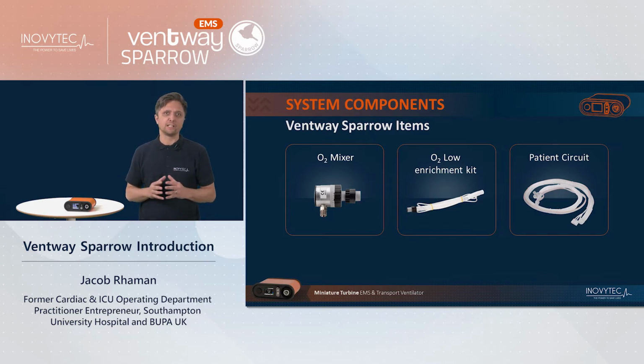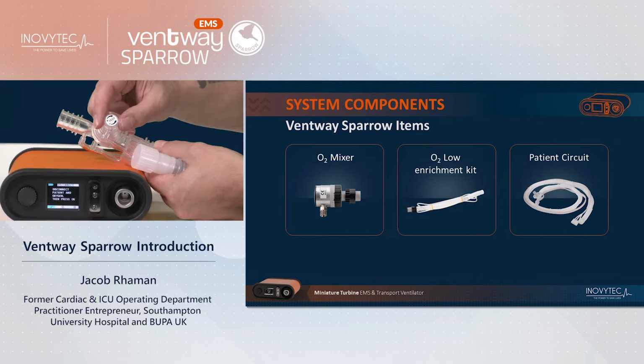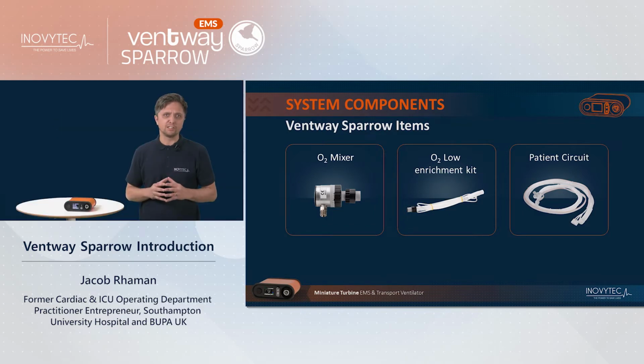The patient circuit has the sensor tubes attached to it. The PEEP mechanism is within the patient circuit. PEEP can be increased by turning clockwise and decreased by turning anti-clockwise. The movement depresses and releases a membrane within the circuit so the clinician can choose the desired PEEP value.